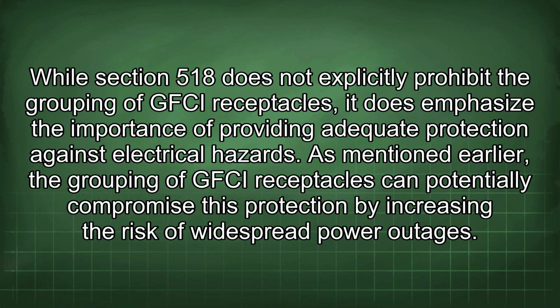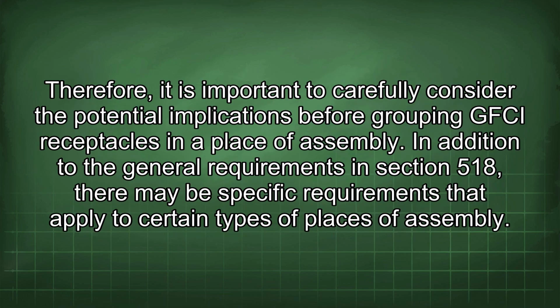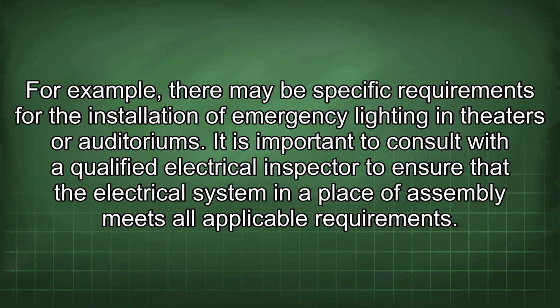While Section 518 does not explicitly prohibit the grouping of GFCI receptacles, it does emphasize the importance of providing adequate protection against electrical hazards. As mentioned earlier, the grouping of GFCI receptacles can potentially compromise this protection by increasing the risk of widespread power outages. Therefore, it is important to carefully consider the potential implications before grouping GFCI receptacles in a place of assembly. In addition to the general requirements in Section 518, there may be specific requirements that apply to certain types of places of assembly. For example, there may be specific requirements for the installation of emergency lighting in theaters or auditoriums. It is important to consult with a qualified electrical inspector to ensure that the electrical system in a place of assembly meets all applicable requirements.